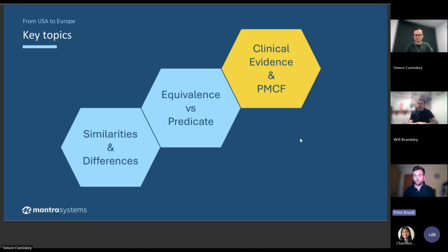So understanding what the clinical benefit of your device's use is, again, similar to intended purpose, sounds very straightforward, but it determines the evidence that you'll need to generate. And then there's a requirement to demonstrate overall acceptability of your benefit risk profile. So clearly we need clinical evidence relating to the clinical benefits, as we just discussed: reduction in pain, improvement in range of motion, improvement in mobility.